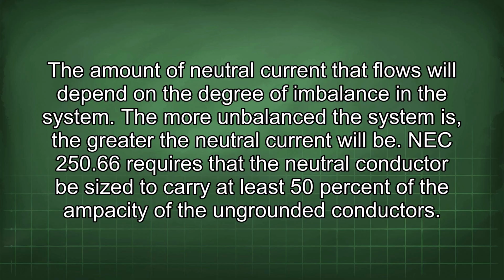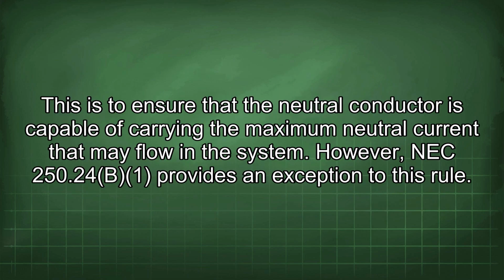NEC 250.66 requires that the neutral conductor be sized to carry at least 50% of the ampacity of the ungrounded conductors. This is to ensure that the neutral conductor is capable of carrying the maximum neutral current that may flow in the system. However, NEC 250.24(B)(1) provides an exception to this rule.